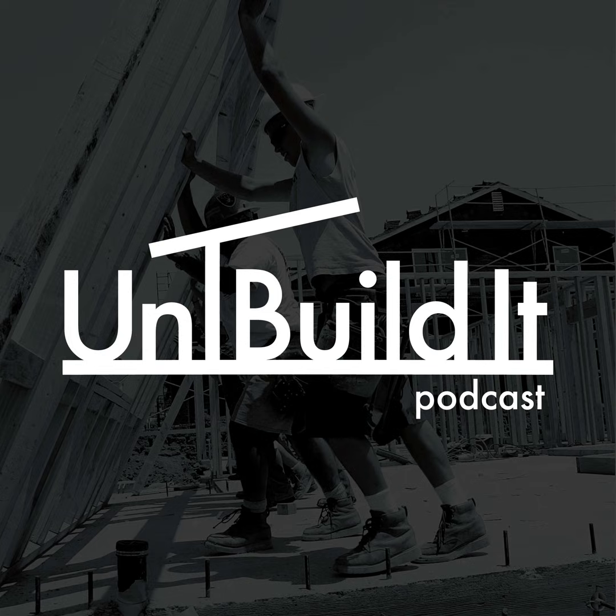Yeah. And there's a 300 or 400 CFM breaking point, or at least there was in the code. I'm not sure exactly how it reads in the 2021, but if your range hood was under 400 CFM, you didn't have to provide makeup air for a long, long time. That's why when you go shopping for fans, you see a bunch of them rated at like 395. We started this conversation with whole house mechanical ventilation, but we're bleeding into the fact that there is a standard that includes not just requirements for whole house mechanical ventilation, but also requirements for spot ventilation, as part of the whole package.